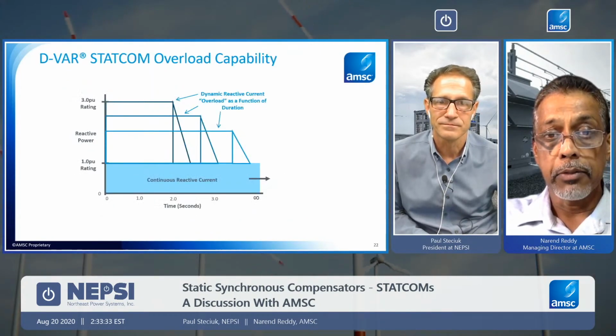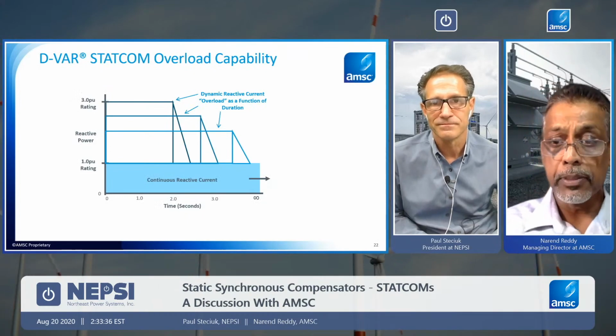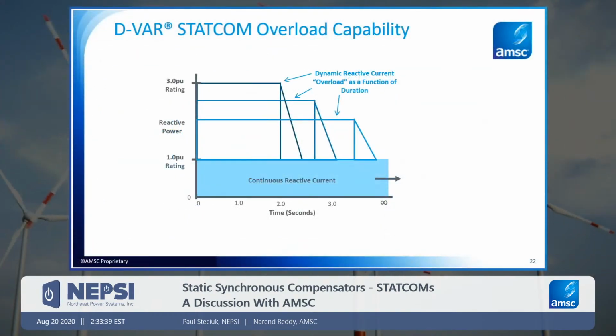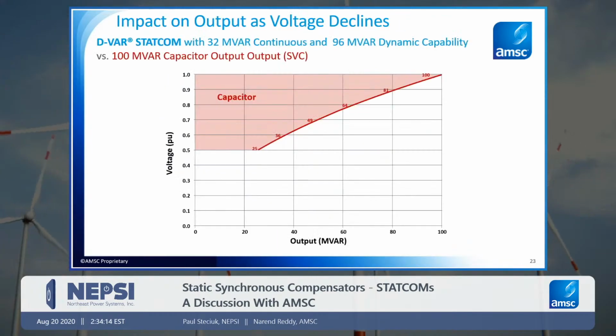The continuous reactive current is something that we would use for normal regulation operations. But this overload capability is also something a little bit flexible for our design. 3 per unit is the maximum that we can control the system to put out. But there are certain applications that may dictate a little bit of extra current for a longer period of time, such as a motor start application that takes 10, 15 seconds or something like that. And so we can actually control the level of overload and have it available for a longer duration. This has been something that we've very commonly used for power quality applications as needed as well. So I just wanted to point that out.